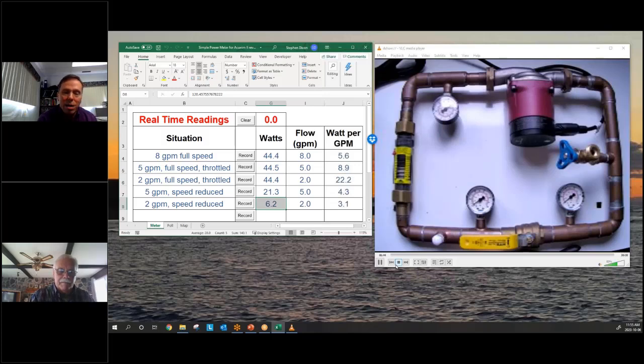The best way to check that is obviously a pump test, but you can also look at your delta T. If it's a chiller system, a heating system or a cooling tower, you check between the supply and return temperature. And if you've got a very low temperature differential, such as 1 or 2 or 3 degrees Celsius, that's a very low delta T, regardless of the type of loop that you have. That's a sign that you're over pumping. You'd sometimes even be better off throttling the system, even though in the example we saw there was not much change. Sometimes you do save a little bit, but honestly, that would mean putting a VFD on, just like the demo we just saw.